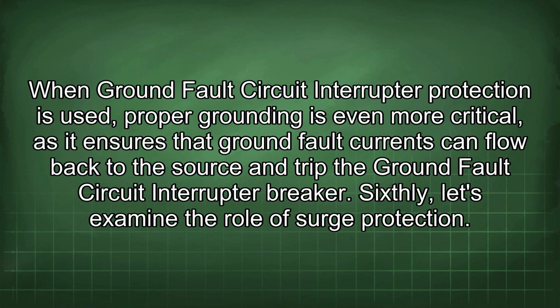When ground fault circuit interrupter protection is used, proper grounding is even more critical, as it ensures that ground fault currents can flow back to the source and trip the ground fault circuit interrupter breaker.